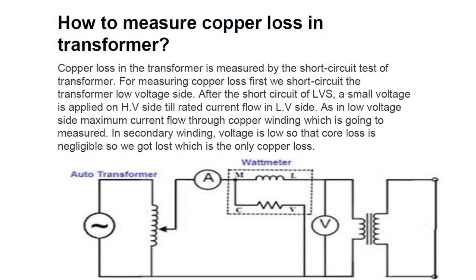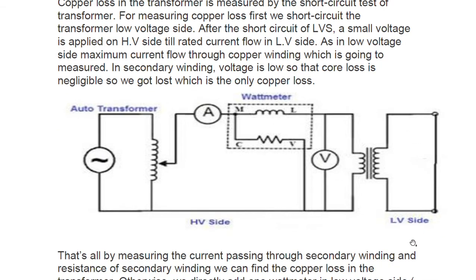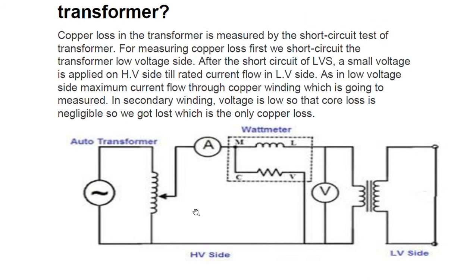Copper loss in the transformer is measured by the short circuit test of the transformer. For measuring copper loss, we first short circuit the transformer's low voltage (LV) side. This is the diagram — this is the LV side (low voltage side) and this is the HV side (high voltage side), where you can vary the voltage. After short circuiting the LV side, a small voltage is applied to the HV side until the rated current flows in the LV side.